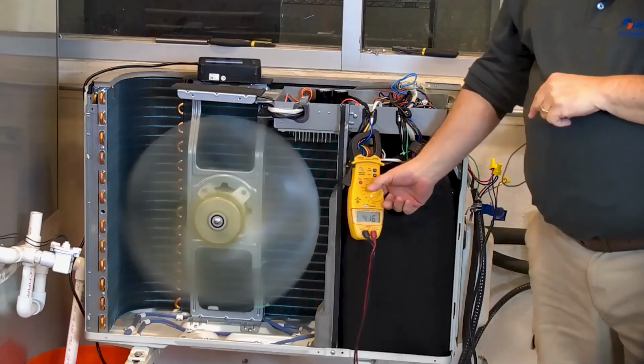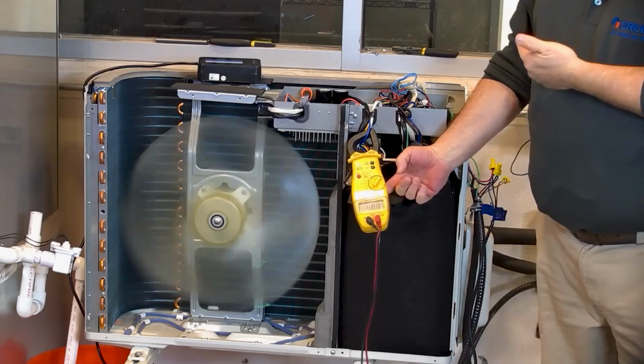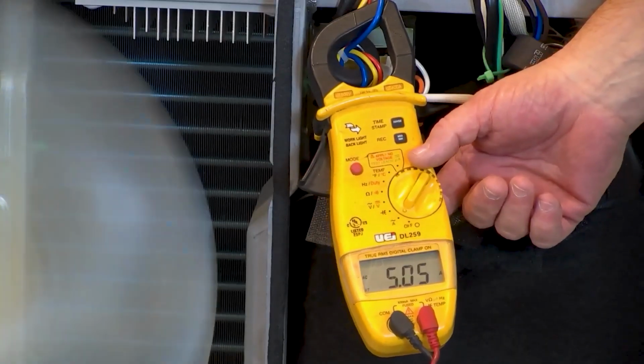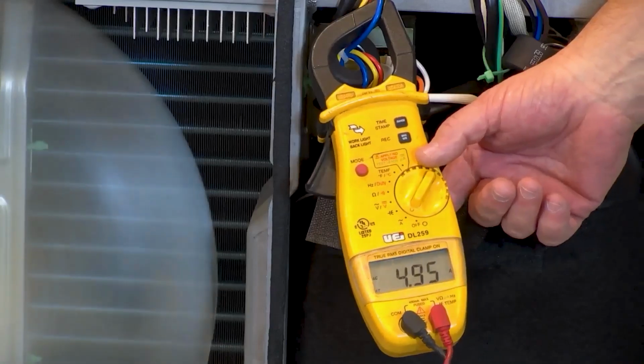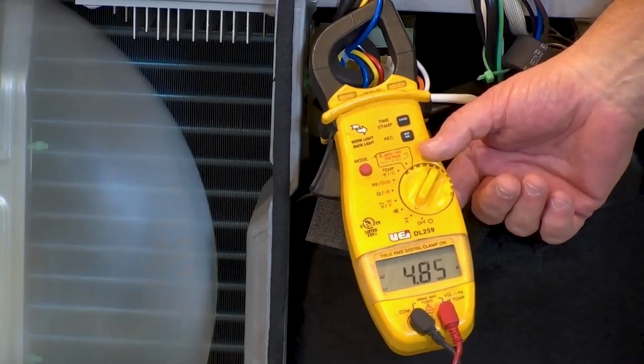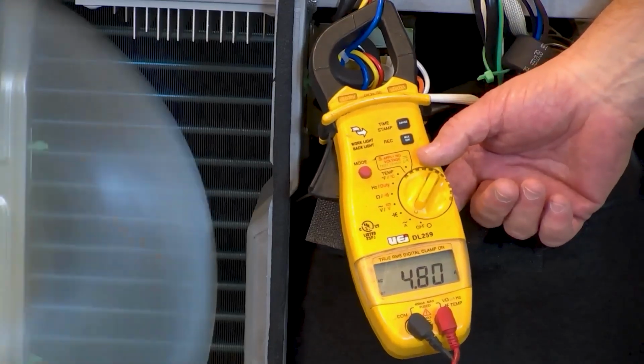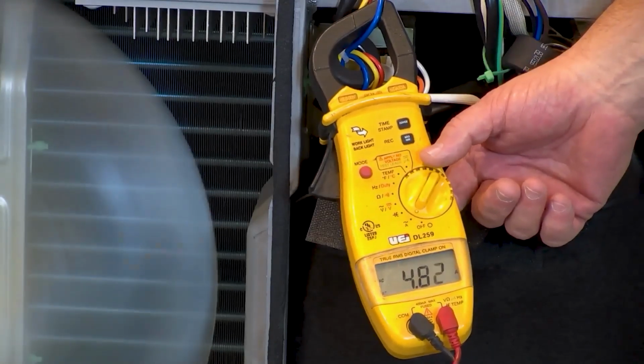So, like Daniel said, we need to ohm out the thermistors. If that's not it, the other thing we can do, and as you can see, I've got the amp probe on it right now, is measure the amp draw of this compressor. If I watch that amp draw keep going up and up, and all of a sudden it goes out on that H7 error code, I'm pushing up against a block. The refrigerant's not flowing. That's what's causing my H5 or my H7. It's not the fault of the compressor itself. Makes sense? See where I'm going with that one? Yep. It could very well be a refrigerant flow problem causing an H5 or an H7 error code.